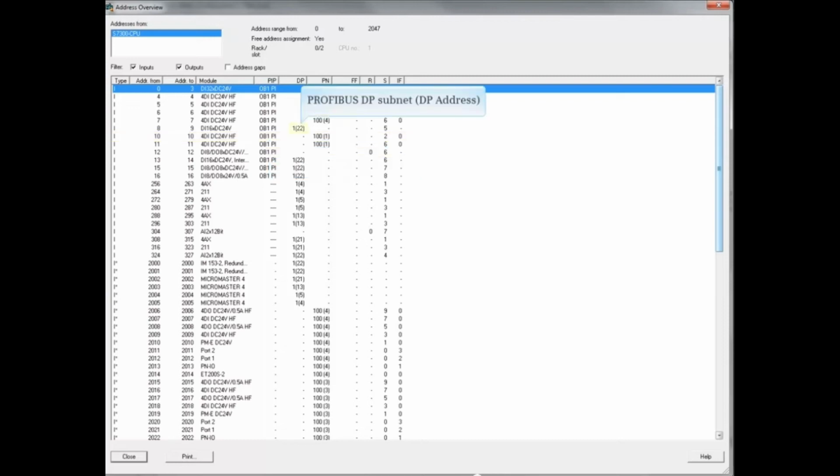If the device is on a Profibus, then DP network with DP address is in parentheses, followed by a Profinet PN network and the device number in parentheses. Or is the device part of the Foundation Fieldbus system, followed by the number of devices in parentheses. Next, what rack is it in, what slot is it in, and if it is an interface module or an interface port, and which module slot or port number it is.